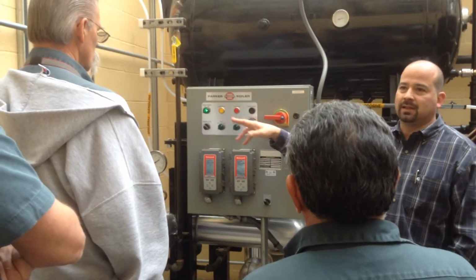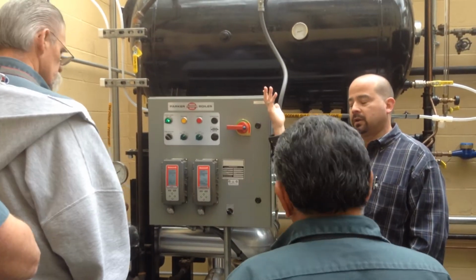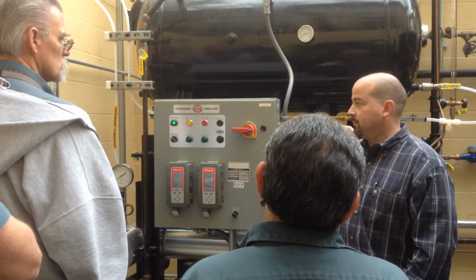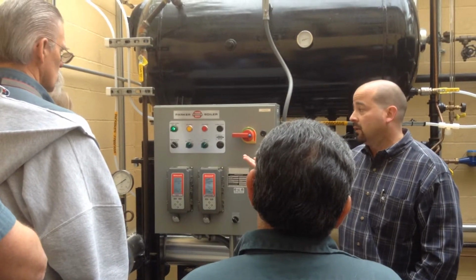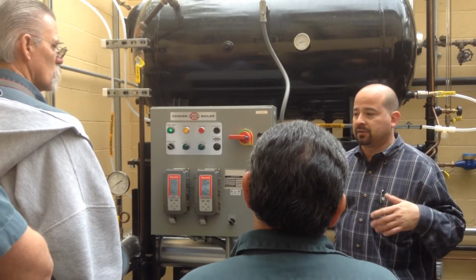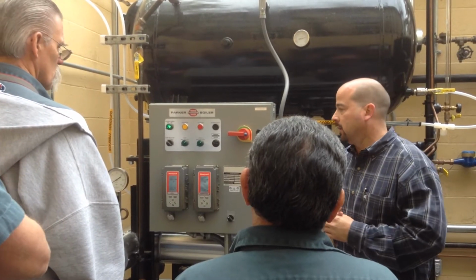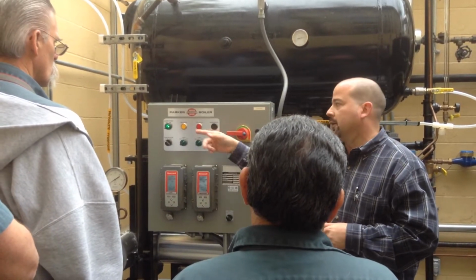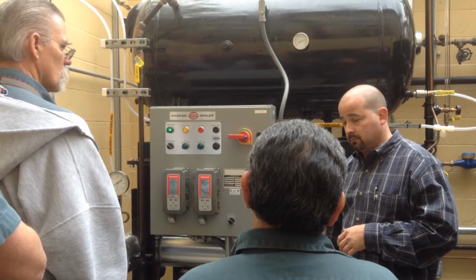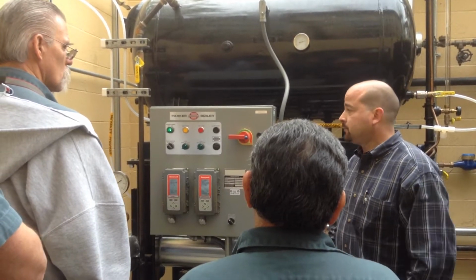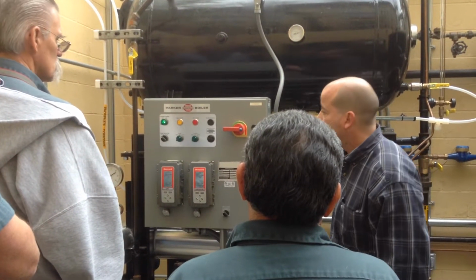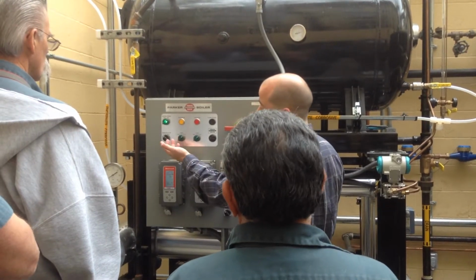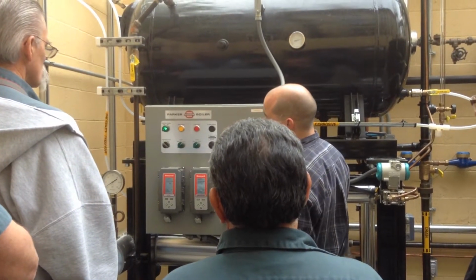Same with the low. Let's say city water got interrupted. The boiler will actually still run for a while until you evaporate water, because you're not bringing in a whole lot of fresh water. But if it goes on low water, it won't allow the pumps to run. It'll protect the pumps, and it'll also go to the Delta V. So pump 1, pump 2 HOA switches, pretty standard.